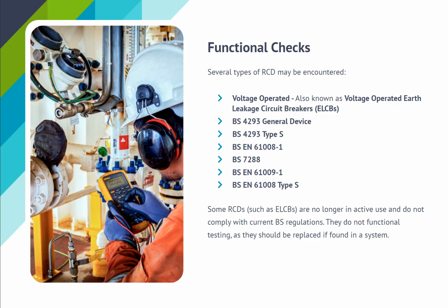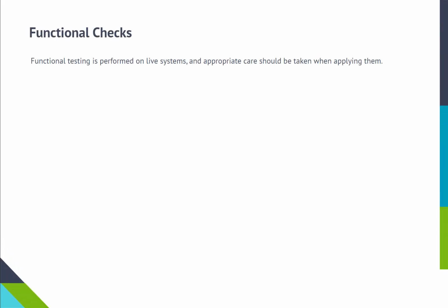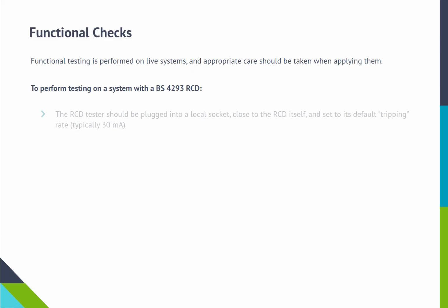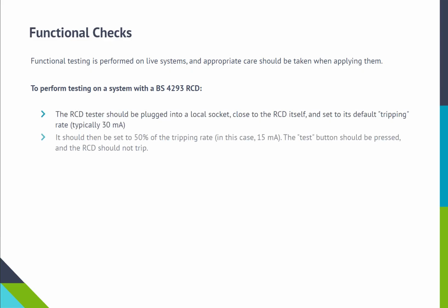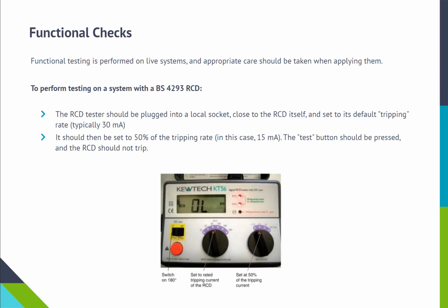BS EN 61008 type S. Some RCDs, such as ELCBs, are no longer in active use and do not comply with current BS regulations. They do not undergo functional testing, as they should be replaced if found in a system. Functional testing is performed on live systems, and appropriate care should be taken when applying them.